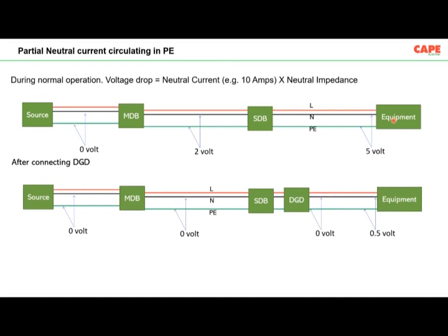In that condition, what people do is, there are a lot of spurious or non-standard products available in the market. One such product is called a digital grounding device. The manufacturer will claim so many parameters. Whatever problems you have, he will call this device a digital grounding device, which I have put as DGD. All solutions are available in this particular device. Practically, what they do is, they simply connect neutral and earth. They short neutral and earth inside this particular equipment.